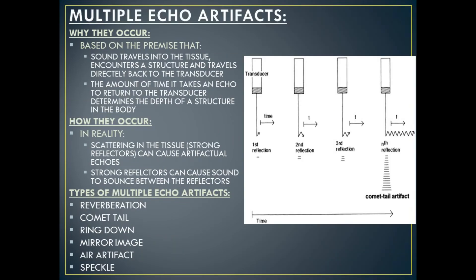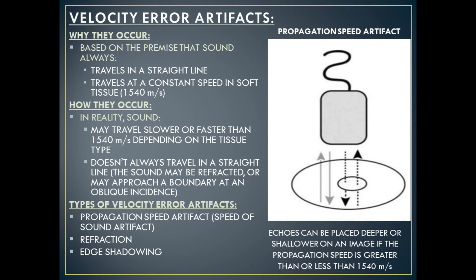Our next category of ultrasound artifacts are multiple echo artifacts. These occur because ultrasound is based on the premise that sound travels into the tissue, encounters a structure, and travels directly back to the transducer, and that the amount of time it takes an echo to return to the transducer determines the depth of a structure in the body. In reality, however, scattering in the tissue from strong reflectors can cause artifactual echoes, and strong reflectors can cause sound to bounce between them. Types of multiple echo artifacts include reverberation, comet tail, ring down, mirror image, air artifact, and speckle.